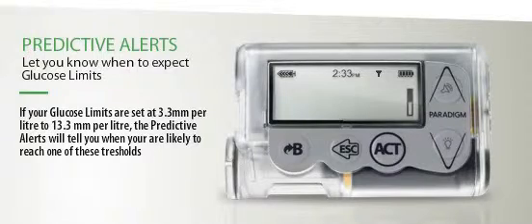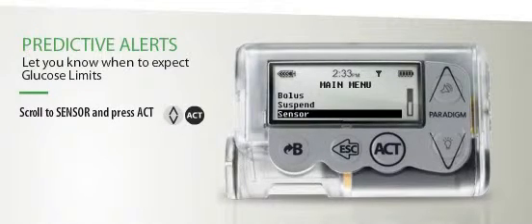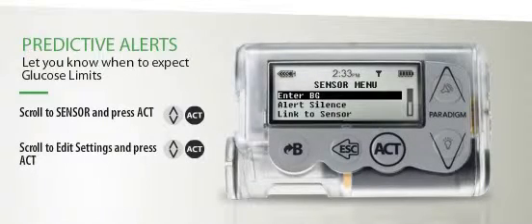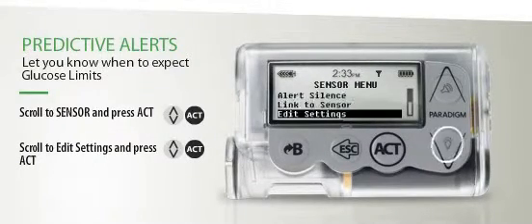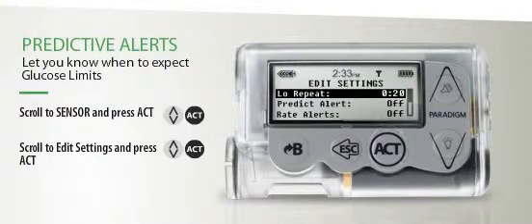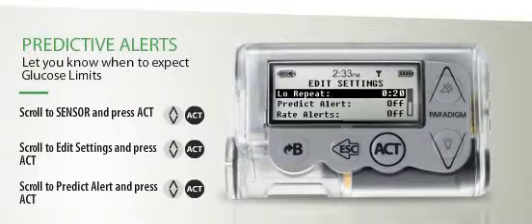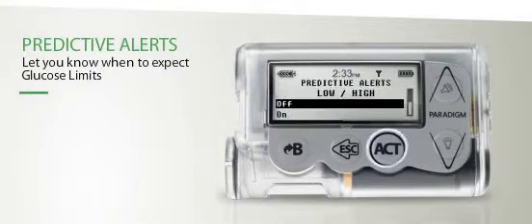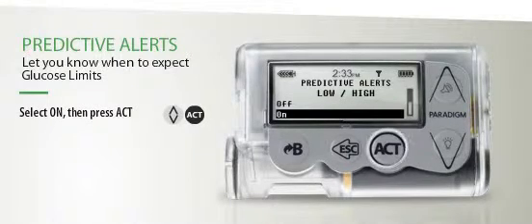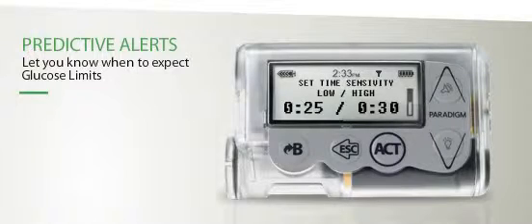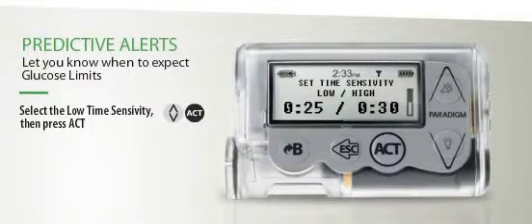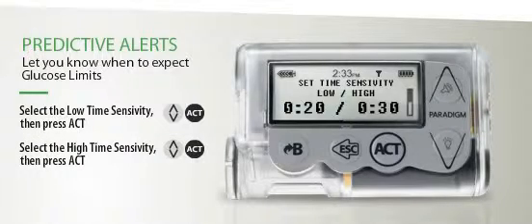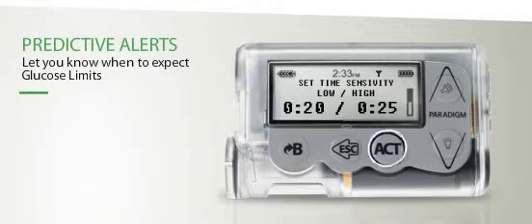To set your predictive alerts, scroll to Sensor, then press Act. Next, scroll to Edit Settings and press Act again. Scroll to Predictive Alerts and press Act once more. Highlight On, then press Act. You are now ready to set the predictive time period, also known as the time sensitivity, for your predictive alerts. All you need to do is set how early you would like to be warned before reaching your low and high limits. You can do this using the up and down arrow keys and pressing Act.